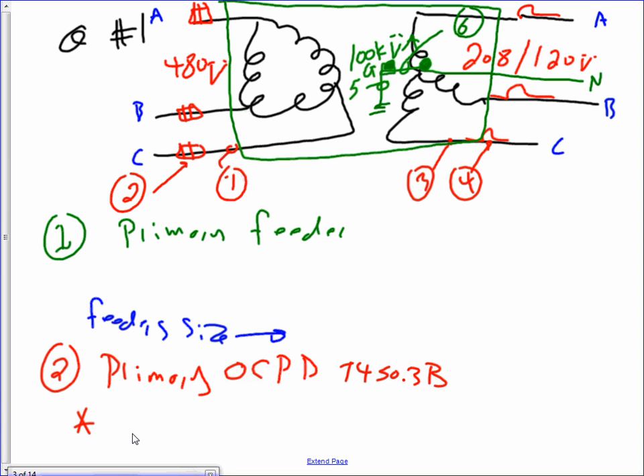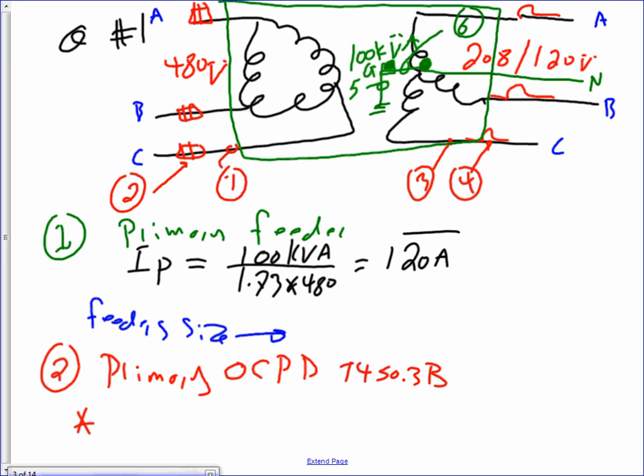Okay, the primary feeder. So let's go ahead and size. When you get to the primary feeder, I'm going to use black here. My primary feeder is number 1. The first thing you need to do is find the current on the primary side of this transformer. You take the 100 kVA and divide it by 1.73 times the voltage on the primary side, which is 480. When we size conductors and fuses, guys, we size them based on the current, not the voltage, for the most part. So that's how you find the full load current of this transformer. And if you do your math, you're going to end up with 120 amps for this transformer.